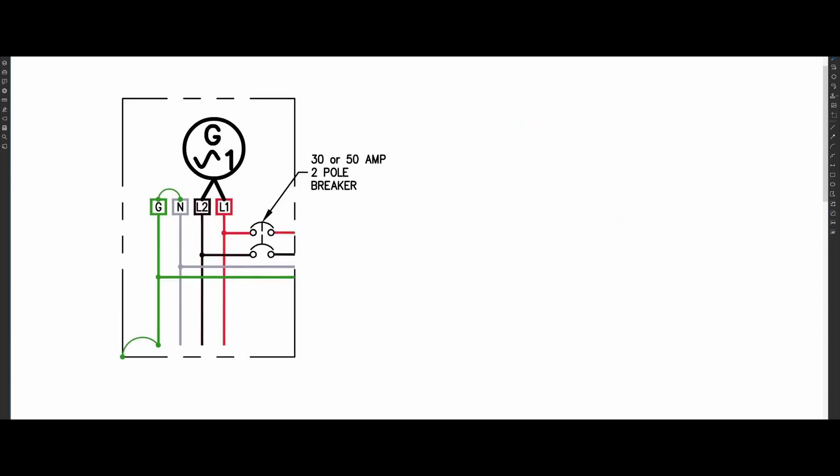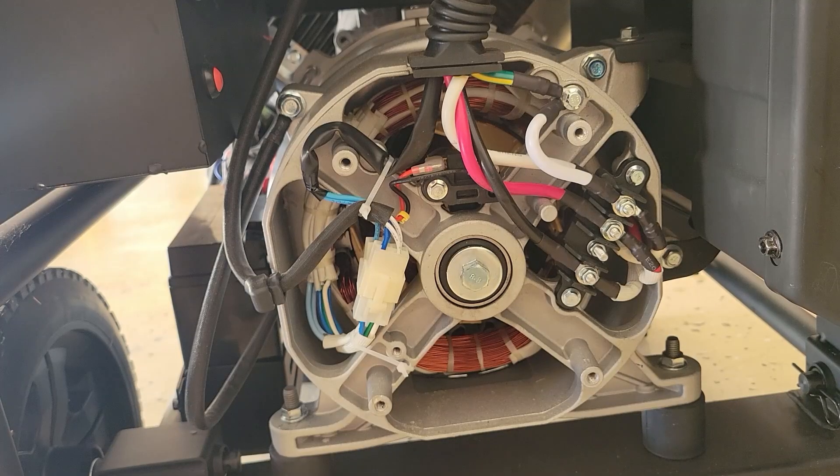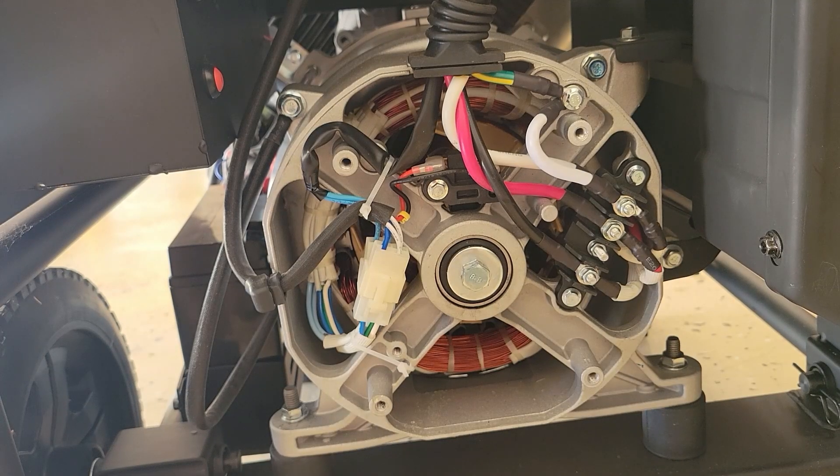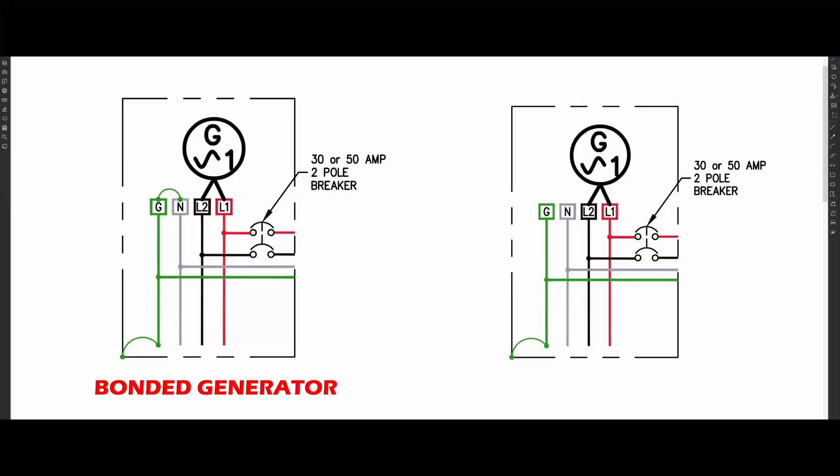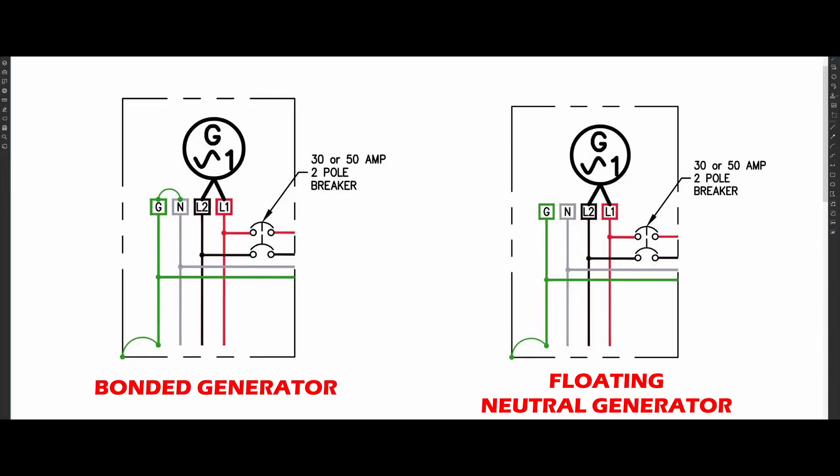Inside a bonded generator, there is a physical bonding jumper that is connecting the neutral and ground bus bars together. A floating neutral generator does not have this bonding jumper. The neutral and ground bus bars are isolated, meaning they are not touching.